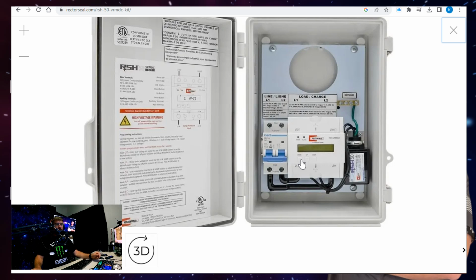And then you can set the delay timer on there. And heaven forbid there was a power surge, but I think automatically it has 3 minutes and you can't avoid that. Then you can set your maximum voltage. So let's say the piece of equipment says the maximum voltage is 256 volts. I'd probably set it to like 250 or 251. And that way, you know, the system's protected. If voltage spikes up, that monitor is going to trip it out of the circuit, so it's not sending voltage to it constantly. And if it does get a really quick surge, it's got this surge protector right in here.